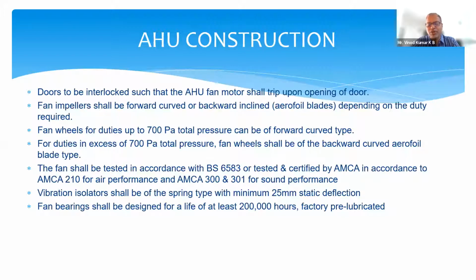That's very important, because when the AHU is selected for pressure levels of more than 700, it should be backward curve. Otherwise it is going to create a lot of noise and will not be able to maintain the pressure you need for the air to reach your last grill or diffuser, because the air has to come, if it's an operation theater, through the plenum and into the space. So if the pressure levels are not correct because the fan is selected wrong, you will not be able to get the air correctly.